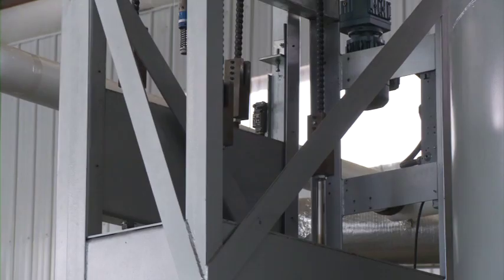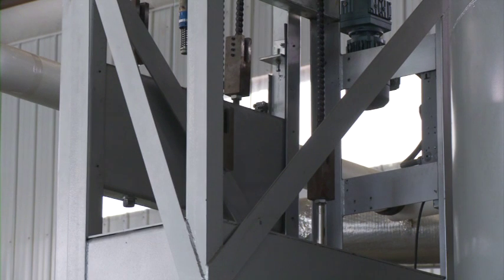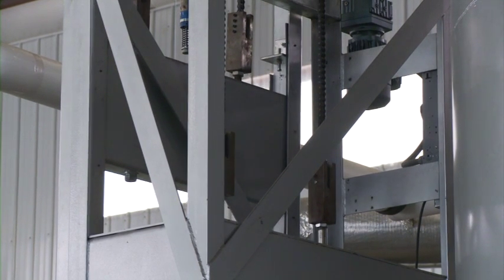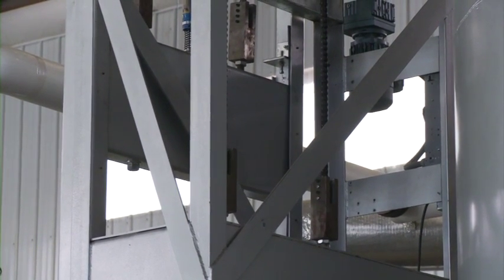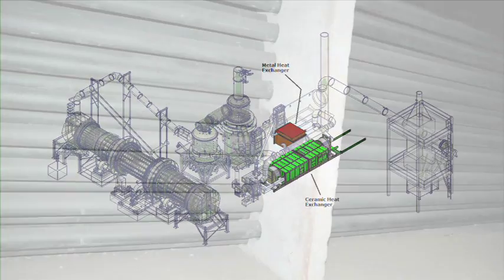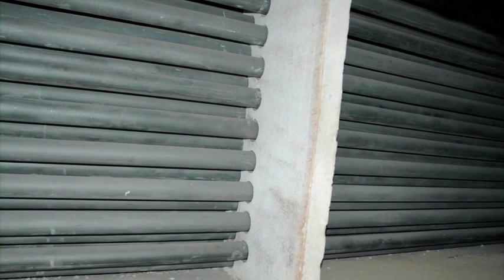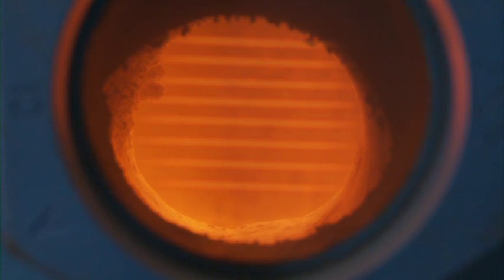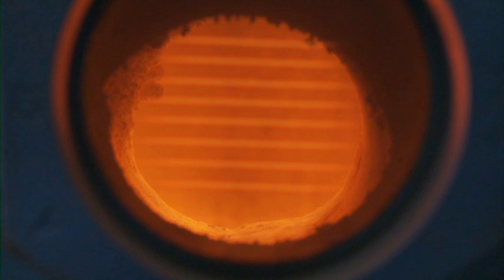When the combustible syngas is mixed with oxygen in the air, it causes the gas to glow and heat to 2000 degrees Fahrenheit. When the gas in the oxidizer reaches 2000 degrees, the valve leaving the oxidizer is closed, diverting energy to the ceramic heat exchanger. This is the view of the ceramic heat exchanger when it is cold. In the background, you can see the glowing tubes of the ceramic heat exchanger when they are at operating temperature. This is where the syngas thermal energy is transferred to the clean air that powers the turbine.